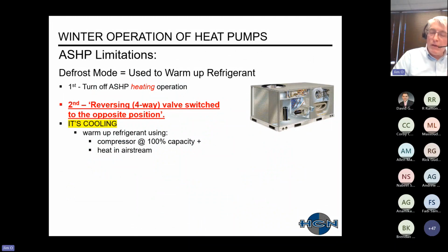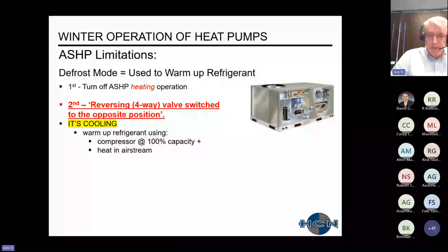Defrost mode is essentially taking the refrigeration system or the rooftop unit and warming up the refrigerant so that it can then go back into heating operation. First, we'll turn off the air source heat pump heating operation. The second thing, I took this right out of a sequence of operation: it says the reversing valve will switch to the opposite direction. That's well and good, but just realize what that's saying is that the heating unit is now going to cooling. We'll warm up the refrigerant by using two items. The first is they'll run the compressors at 100% capacity to add as much heat as possible.